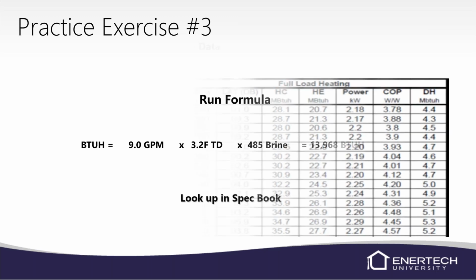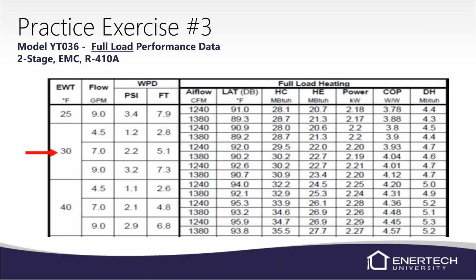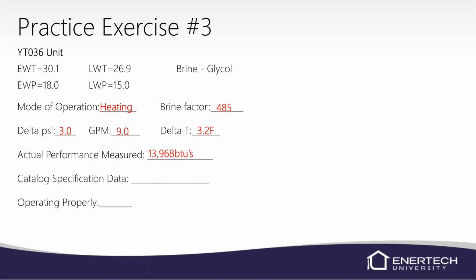We take that number and match it to what's in the book. Again, 30-degree entering, 9 GPM at 1240 CFM, 22,700 BTUs. Well, 10% of 22,700 is about 2,270 BTUs. So we're within 10%, a minimum of about 20,000 BTUs. And we're at 13. One thing I would say on this example here, obviously it's not operating properly.